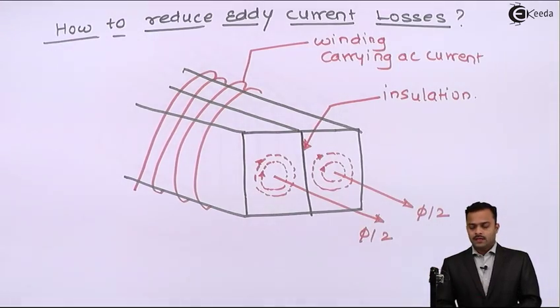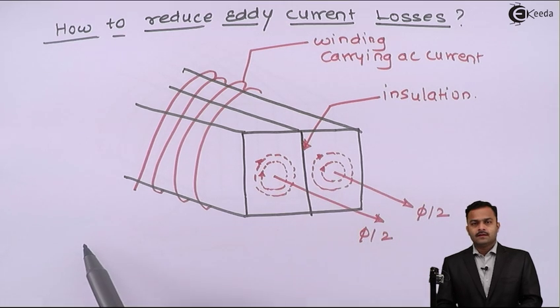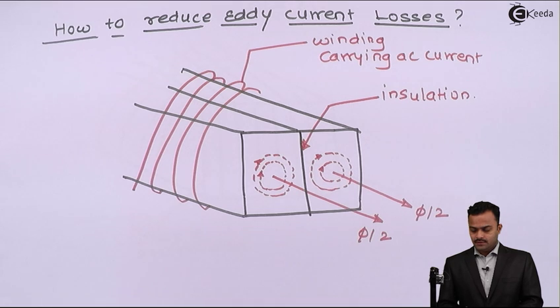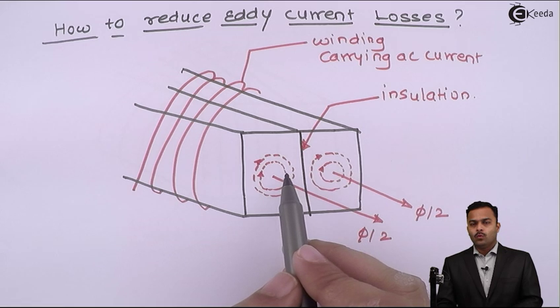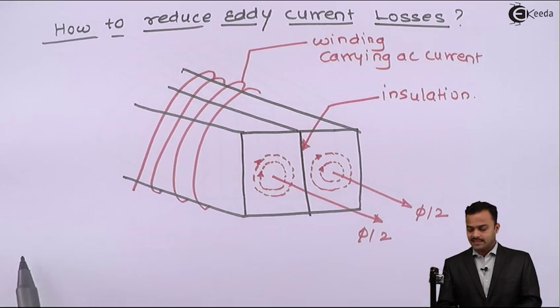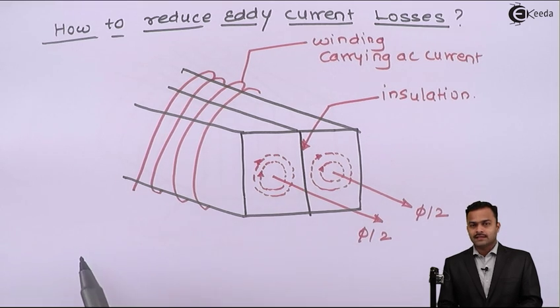We will split the core into two lengths so that the length will get half, and voltage induced in each section will be one-half of the earlier case, so that eddy current will reduce considerably.